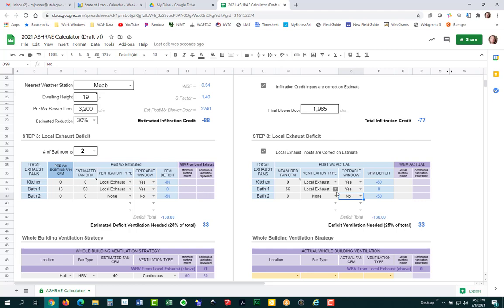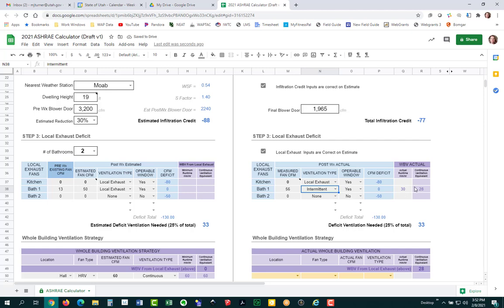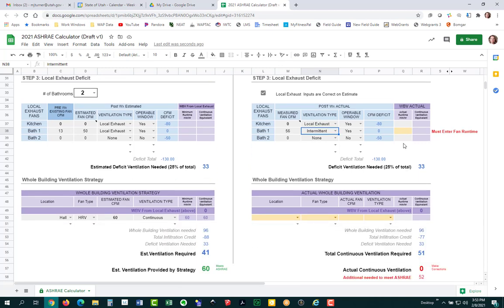If we decide to use bathroom one's fan as part of our whole building ventilation strategy by selecting intermittent, then you have to put in the actual runtime. On this side of the calculator, it won't estimate the runtime for you — you'll have to figure out the runtime yourself. The new calculator you receive will not have any old data in it; everything will be blank. When you change from local exhaust to intermittent exhaust, the runtime box turns yellow because you need to enter a value.